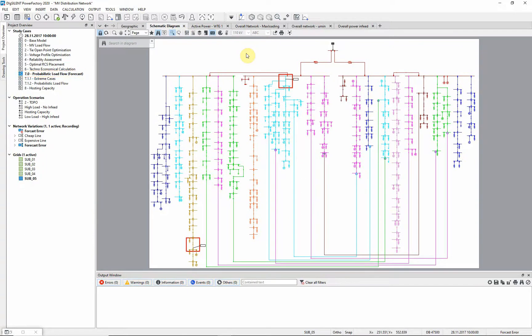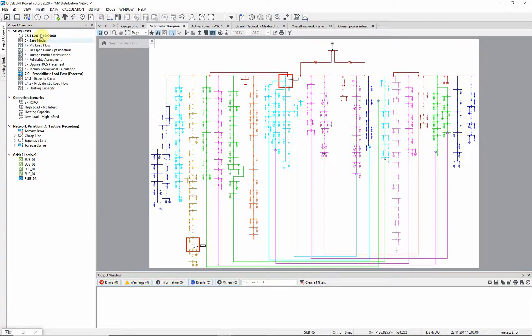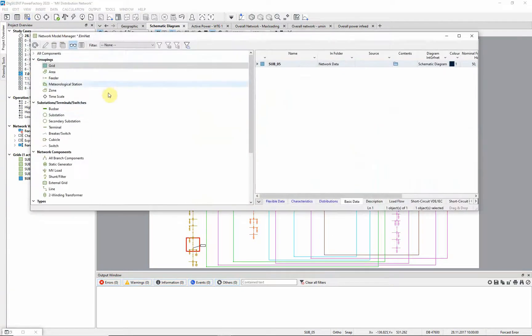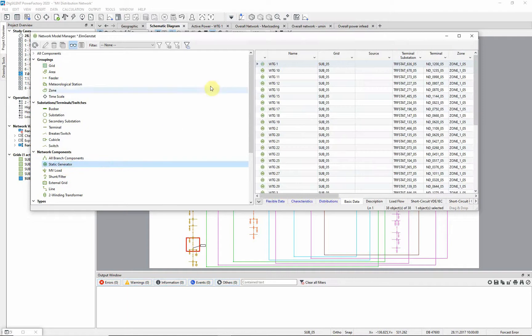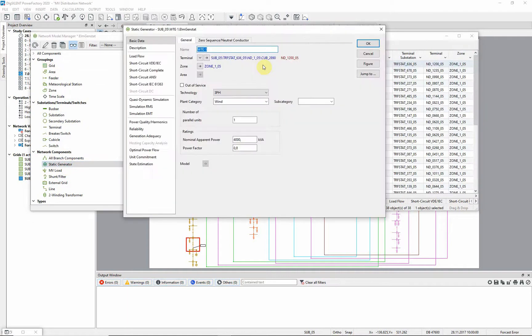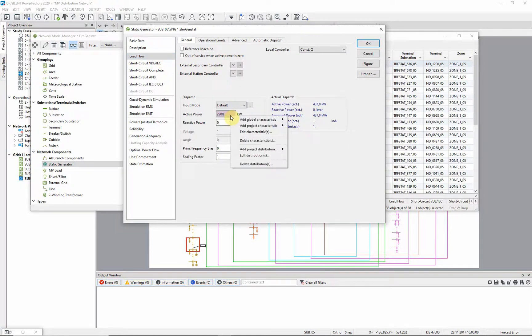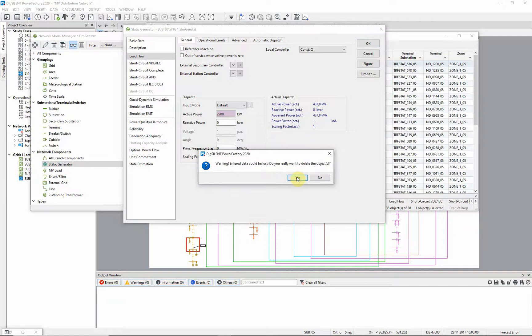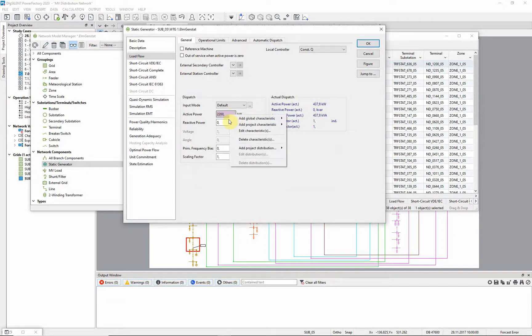For the probabilistic analysis, distribution functions are necessary. We will assign a normal distribution to the active power value of a wind generator, in order to consider a forecast or measurement error. For this purpose, we right click on the active power value, which is already modified by our characteristic. We will first delete an existing distribution and then select add project distribution.